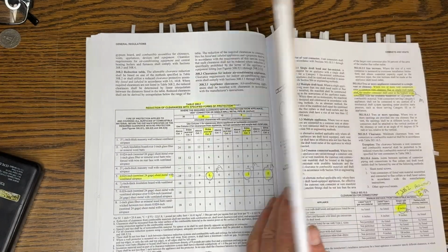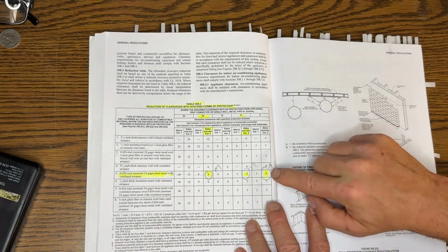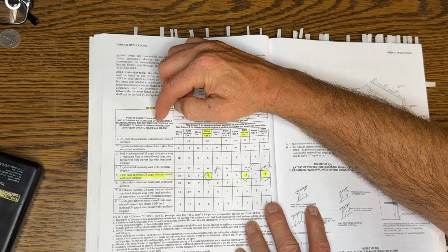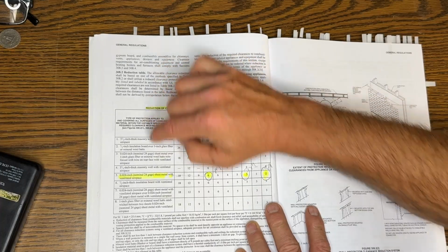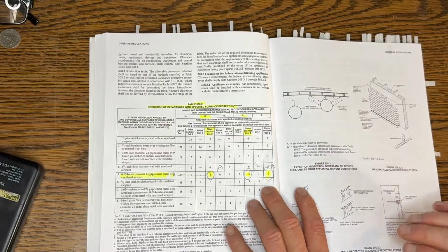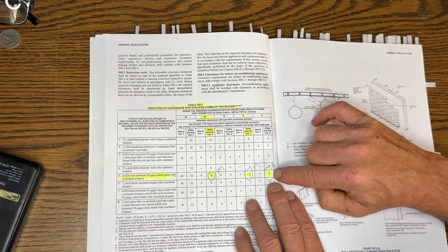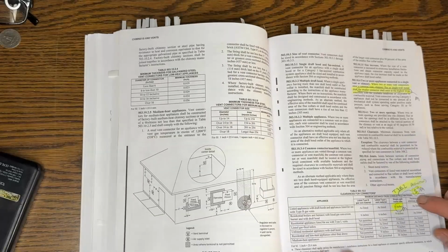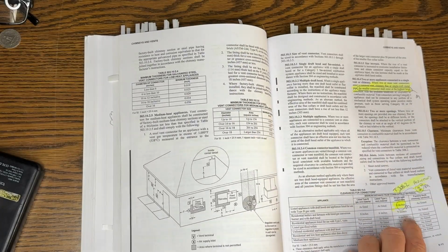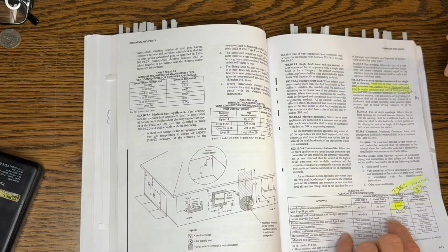Required clearance with no protection. Minimum distance from combustible material is 6 inches, but I can reduce it to 2 inches if I have a protection covering. Yeah, so if I had like a shield made of at least 24 gauge, instead of having 6-inch separation to combustible materials, I can go to 2 inches with that protection. That's how this works. So just keep in mind that 6 inches drops to 2 inches based on that. A little bit convoluted with multiple tables, but it's important to know where that is.